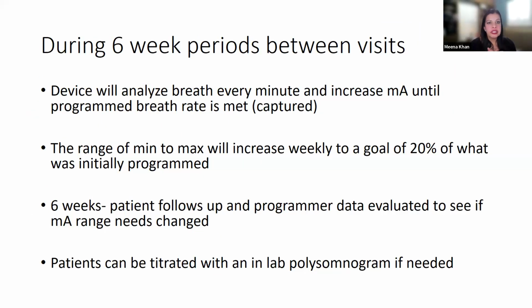During this 6-week period between visits, it's going to analyze the breathing every minute, and again, increase the milliamp in that range that's set until breath rate is captured or met. And then the device increases that min and max range weekly to a goal of 20% after 6 weeks. At 6 weeks, the programmer data is evaluated, and we see if that milliamp range needs to be changed, how the patient is doing, are they tolerating it, and then reset it, and then have them go home for another 6 weeks, and then come back for another appointment. If we're having difficulty titrating them, or it looks like we're not getting capture, or the patient may not be tolerating the therapy very well, you can titrate patients in the lab. Typically, we have a representative from the company come and do that if we're not really being successful with this outpatient programming.